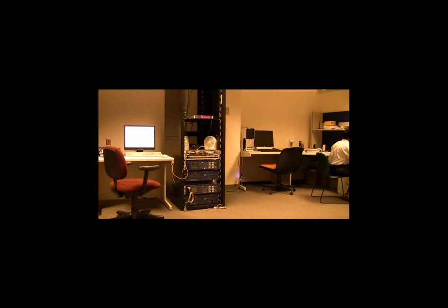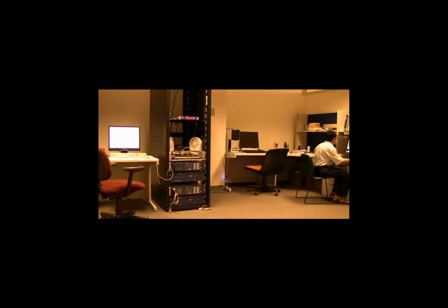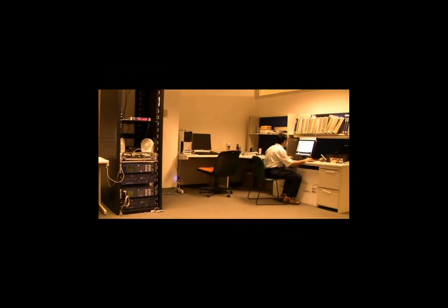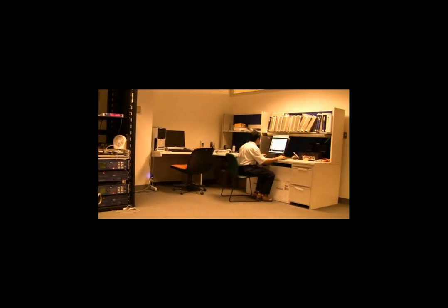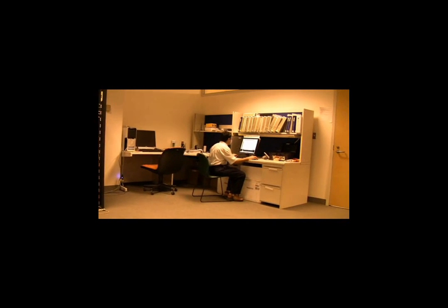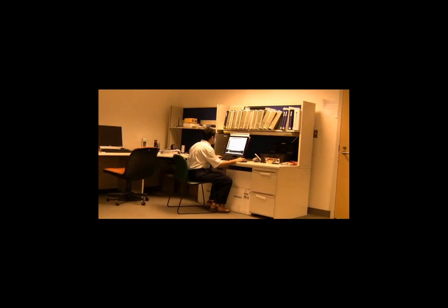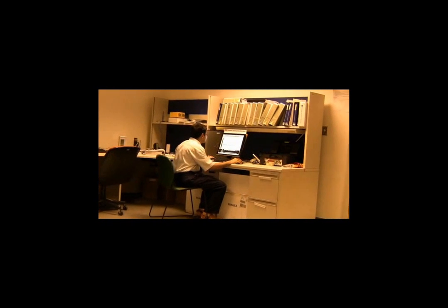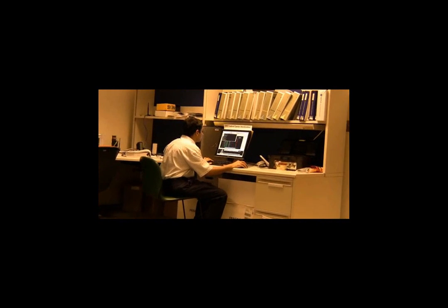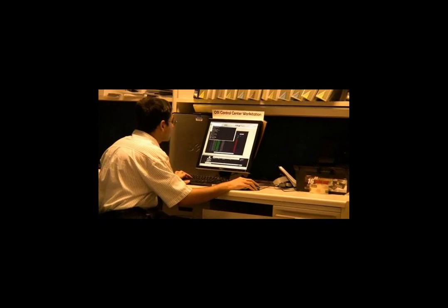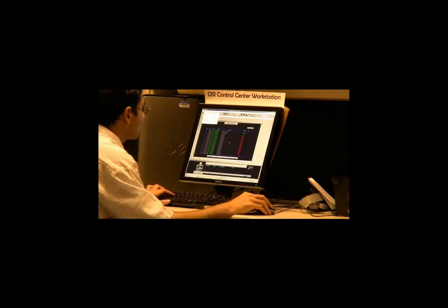The evaluation team at TCIP is developing a toolchain to allow automated assessment of arbitrary control network configurations for compliance to NERC CIPs and security best practices, using technologies like first-order logic to model network entities, connectivity and logical dependencies, and rewriting logic to model maintenance procedures for the power grid. It determines vulnerabilities to external attackers and ranks operating procedures according to their security risk.